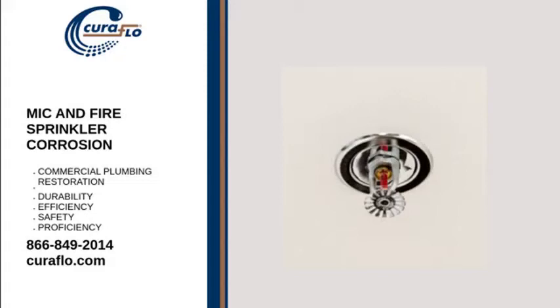In 1996, the NFSA, National Fire Sprinkler Association, led a survey that requested information regarding experiences of sprinkler system failure via a questionnaire in its magazine for members. 40 responses were received from NFSA members in Canada and the US, and the NFSA concluded that MIC was widespread. It is however important to note that the qualifications of persons determining the type of corrosion are not known. This is particularly relevant as it is difficult to distinguish MIC from other types of corrosion.